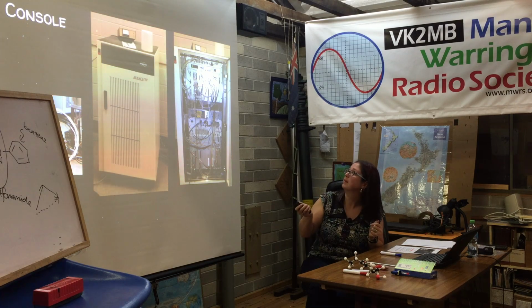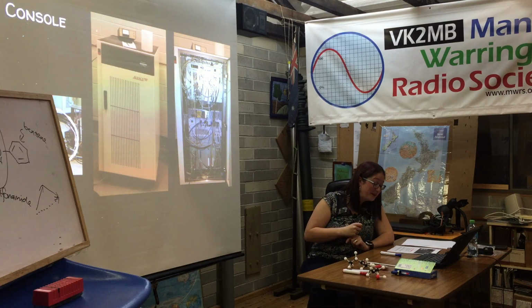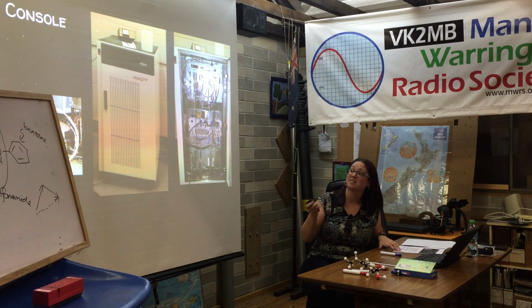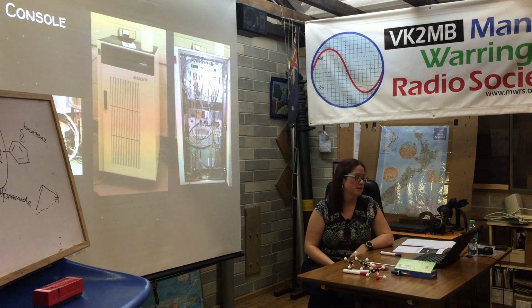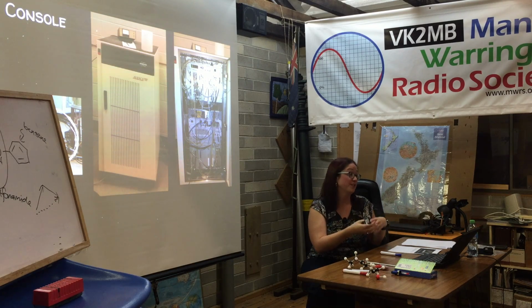That's the console, big box. You've got the components. You've got the AQS rack, the acquisition rack. You've got a variable temperature unit. You have an amplifier, transmitter, and this thing down here is the Bruker smart magnet system, which is responsible for some things that I haven't talked about and won't talk about. The acquisition rack up here is responsible for the generation of the RF pulses, and it receives, amplifies and digitizes the signal, which is first captured by this preamplifier and then directed back here and digitized. Fourier transforms are done in the software. The console is responsible for acquiring the time domain signal, and then that's processed on the workstation.